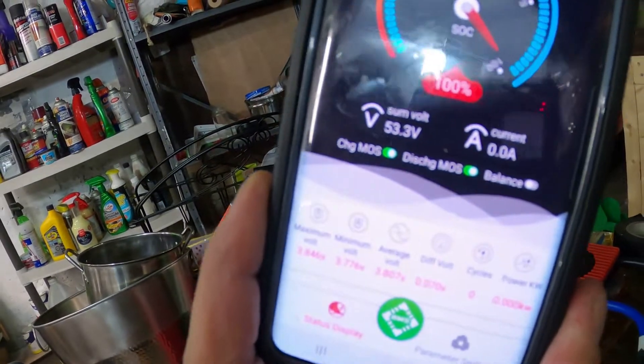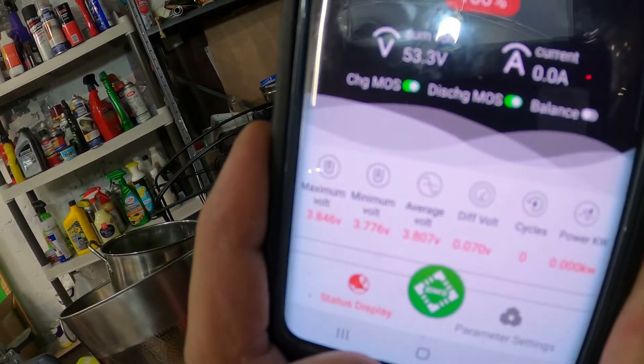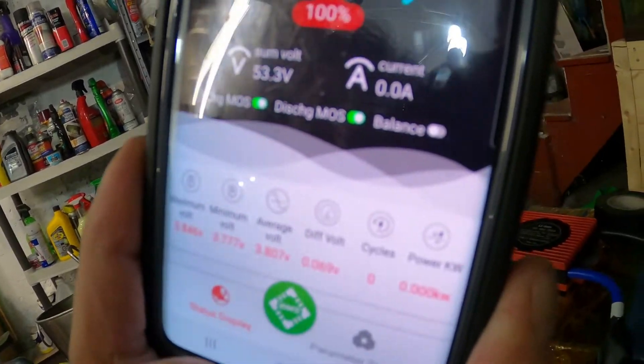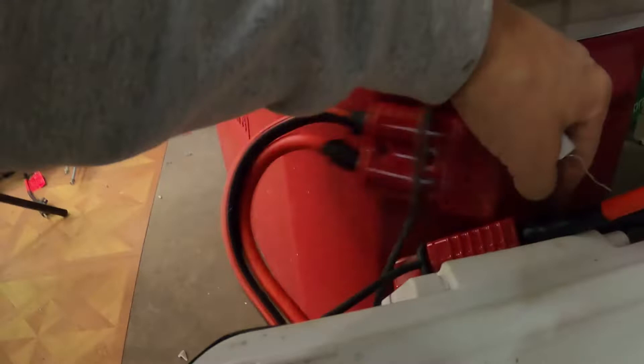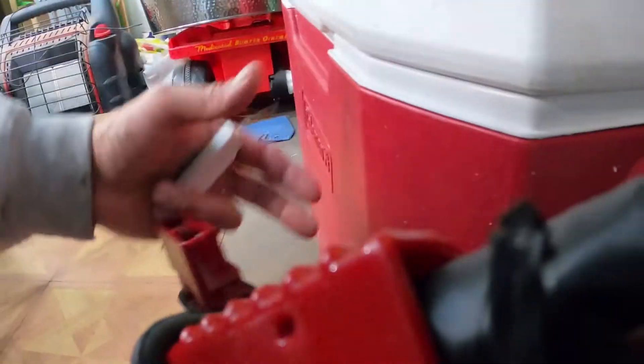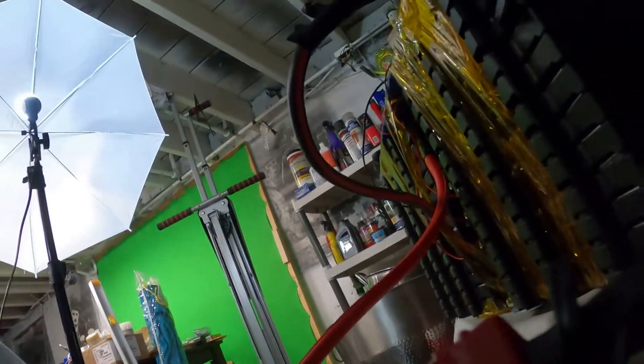I have a 70-amp breaker — it's a 70-amp breaker because this is copper-clad aluminum and the highest continuous amperage is 75, so I went with 70 amps. The system is on and working right now. Maximum voltage is 3.846 volts per battery, minimum is 3.776 volts, and the total voltage out of this battery pack is 53.3 volts. I'm going to plug in the MC cables right here.